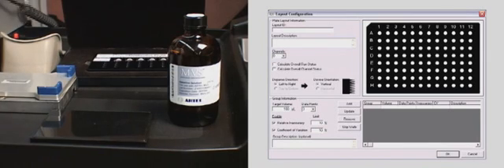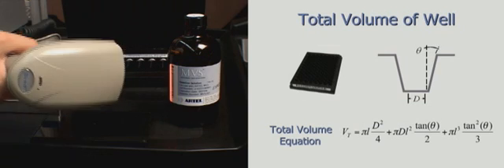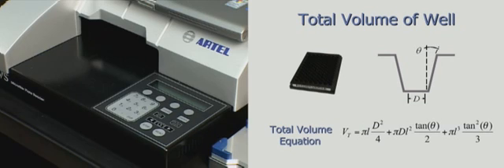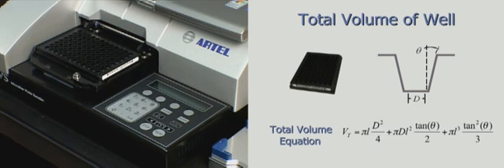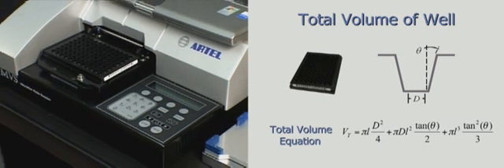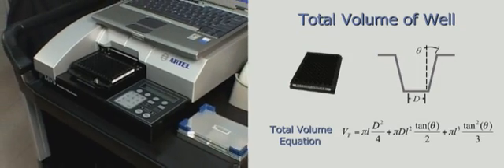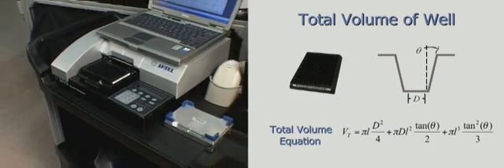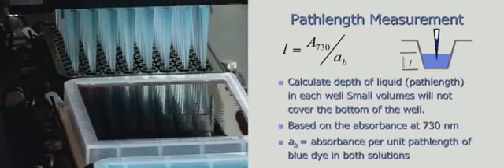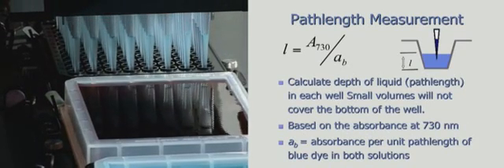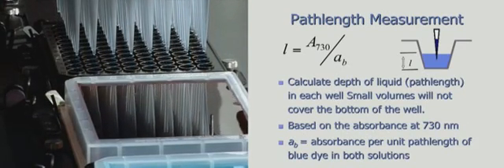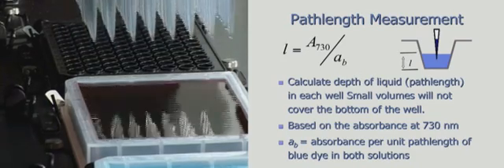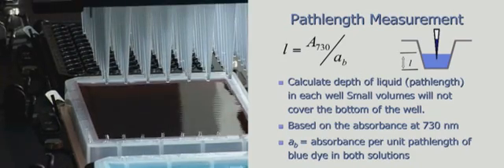Scan the proper barcodes on the sample solution and the diluent bottle. Use a verification plate for a true volume measurement that is traceable to NIST. Alternatively, optically clear, flat-bottom microtiter plates may also be used once they are added to the plate library. Fill each well of the verification plate using MVS diluent solution. The diluent serves as an internal standard, by which the path length within each well is individually measured.